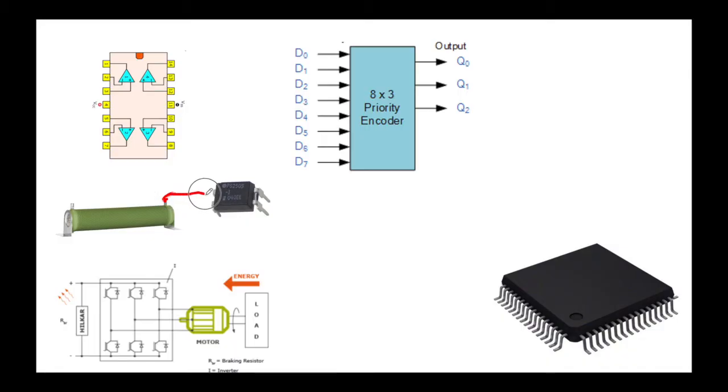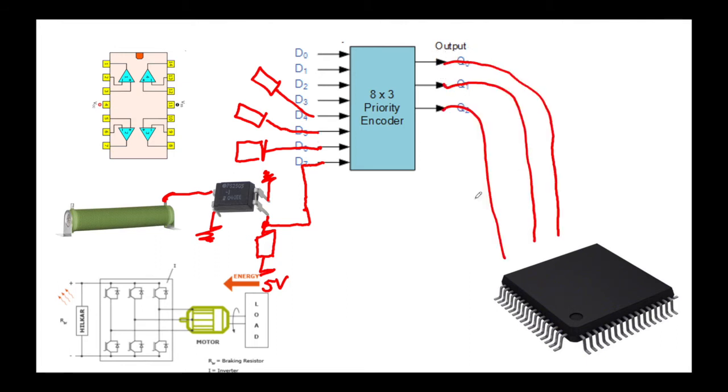Information about whether the brake resistor is connected is transmitted through the optocoupler. From the optocoupler output, after the pull-up resistor, one line enters the encoder input. In this format, information about whether the brake resistor is installed is given to the microcontroller. The encoder, having received 8 different signals, communicates to the microcontroller through 3 pins.